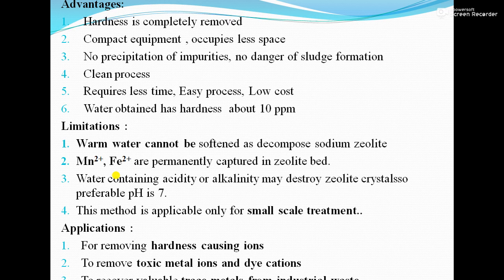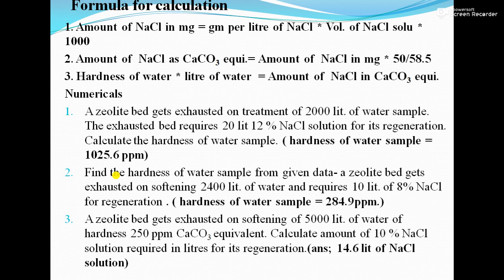The formulas for calculation in zeolite numericals are three stepwise formulas. Formula 1: Amount of NaCl (mg) = gram per liter of NaCl × volume of NaCl (L) × 1000. Formula 2: Amount of NaCl as CaCO₃ equivalent = Amount of NaCl (mg) × 50 / 58.5. Formula 3: Hardness of water × liters of water = Amount of NaCl as CaCO₃ equivalent.